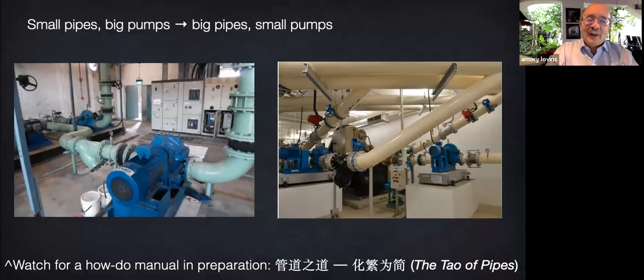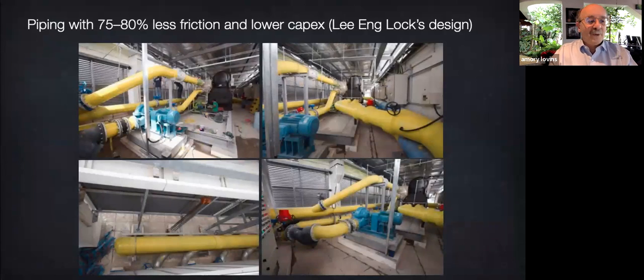Let me show you a few more of the nice photos that they discuss, kindly supplied by Peter Rumsey and by his and my mentor, Lee Eng Lock. In the Singapore biotech plant, in the lower left photo, the lower gray pipes feeding up into the manifold are slanted to match the direction of flow, like merging into traffic. The pump in the other three photos is raised up on a plinth to meet the pipe, rather than bending the pipe down to the floor-mounted pump and then back up again. The big pipes are even stacked vertically to save floor space, because Singapore has very high land prices.